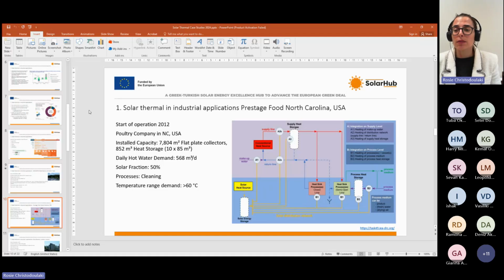What does it mean? It means that the solar thermal system can supply 50% of the total heat demand of the Prestage Foods factory. It is used in the cleaning processes, which are a lot in that specific factory, and the temperature range demand is over 60 degrees Celsius. And in this picture, you can see a simplified hydraulic diagram of the processes.